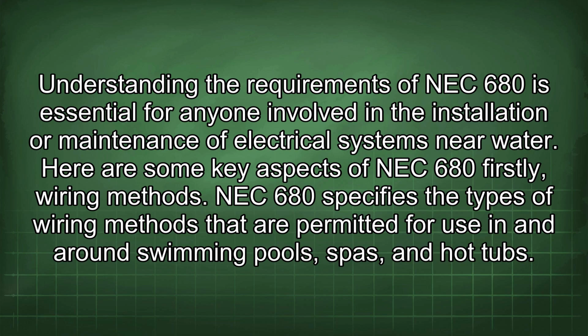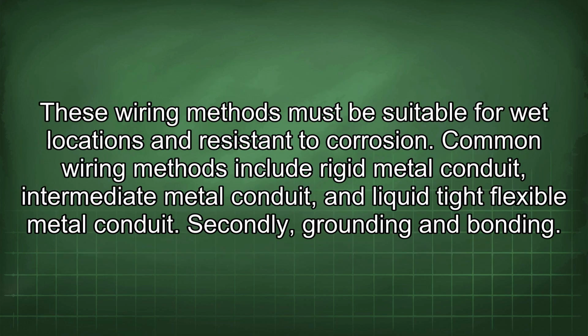Firstly, wiring methods. NEC 680 specifies the types of wiring methods that are permitted for use in and around swimming pools, spas, and hot tubs. These wiring methods must be suitable for wet locations and resistant to corrosion. Common wiring methods include rigid metal conduit, intermediate metal conduit, and liquid-tight flexible metal conduit.